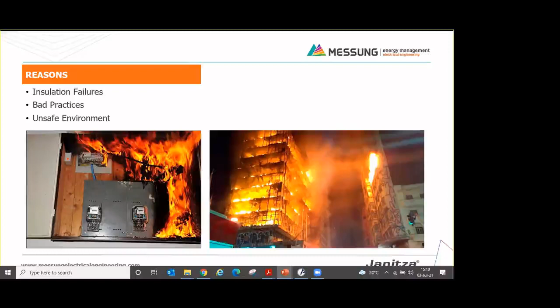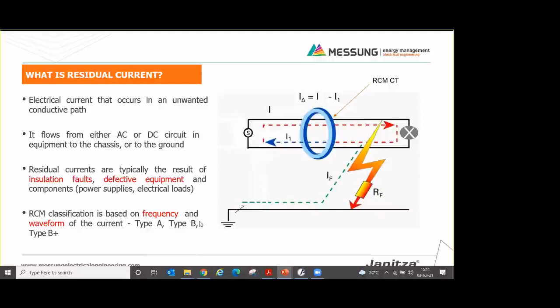So let's see what residual current is. In simple terms, it is a parasitic current which flows through an unintended conductive path. It means in normal working condition, the current should originate from the phase conductor, pass through the equipment, and return back to the system through the neutral conductor. But due to some failures such as insulation fault or phase-to-ground fault, the residual current flows from phase to the earth. This is unwanted. And residual currents can be classified into three types depending upon their frequency and waveform, which are type A, type B, and type B+, which we are going to cover in further slides.